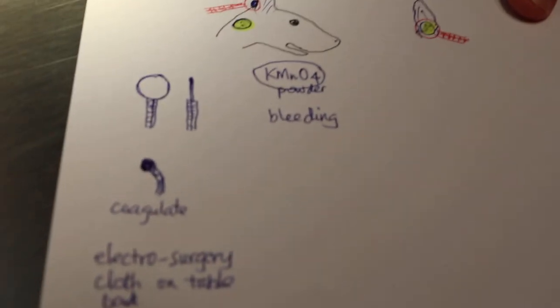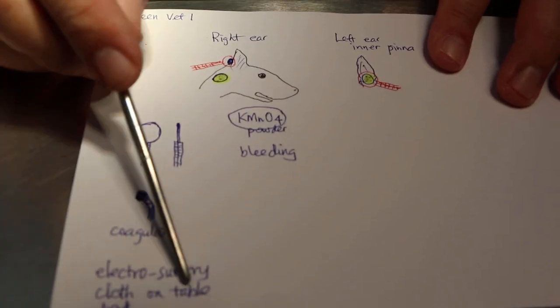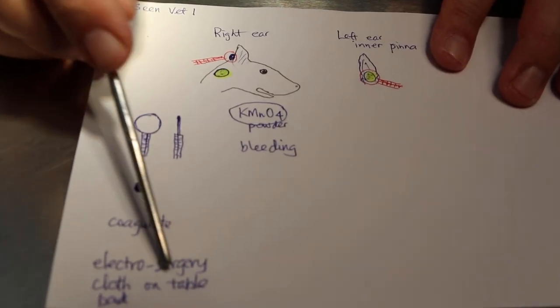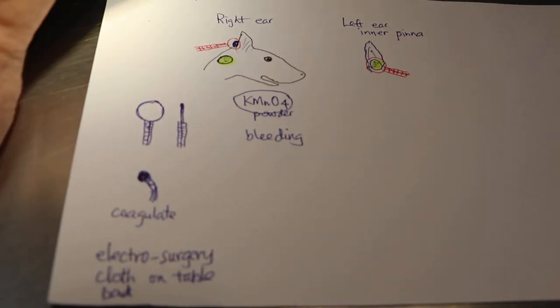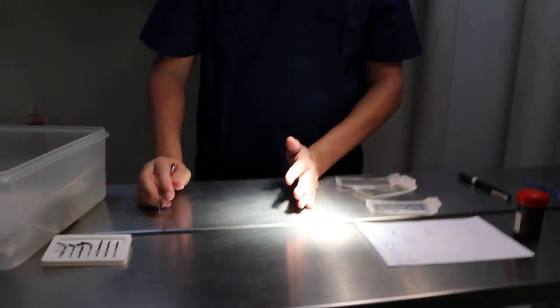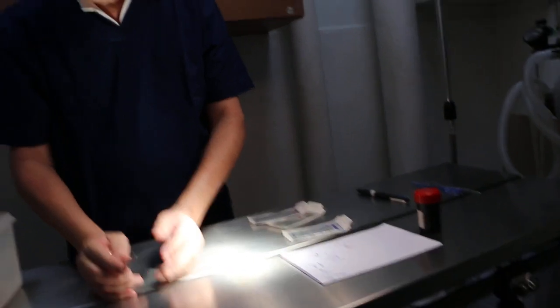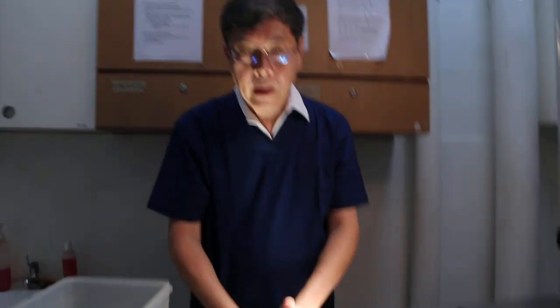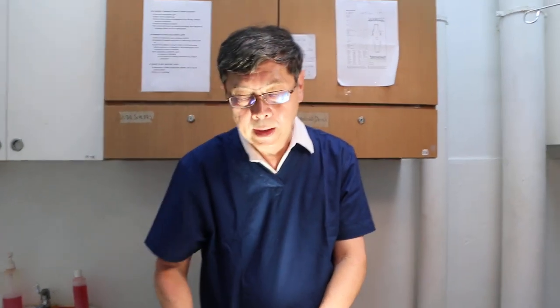Now, the other thing is you need to have a cloth on the table so that the vet wouldn't get electroshock, electrical shock. Because sometimes the hand touches the metallic operating table. You can see here. So, you put a cloth here. Then at least when you operate it touches the cloth and does not touch the metallic table which would cause electric shock.